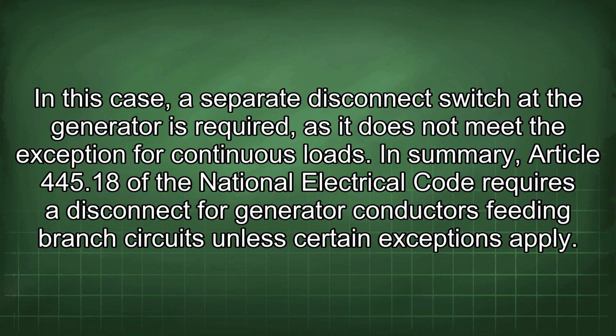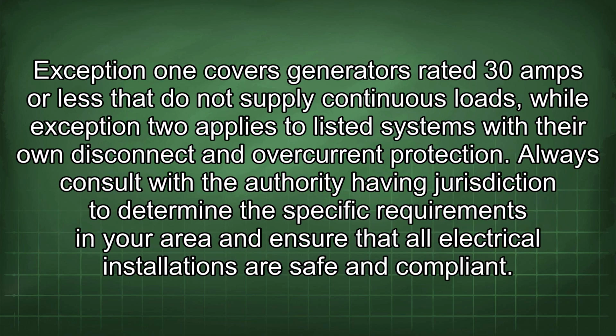In summary, Article 445.18 of the National Electrical Code requires a disconnect for generator conductors feeding branch circuits unless certain exceptions apply. Exception 1 covers generators rated 30 amps or less that do not supply continuous loads, while Exception 2 applies to listed systems with their own disconnect and overcurrent protection. Always consult with the authority having jurisdiction to determine the specific requirements in your area and ensure that all electrical installations are safe and compliant.